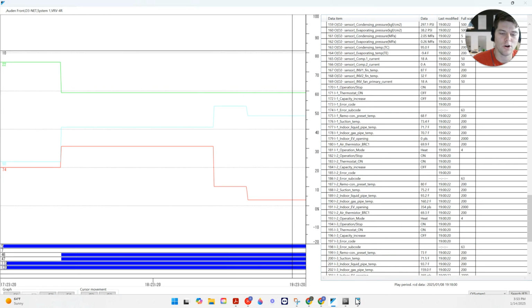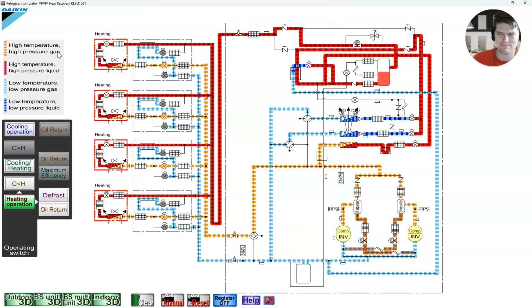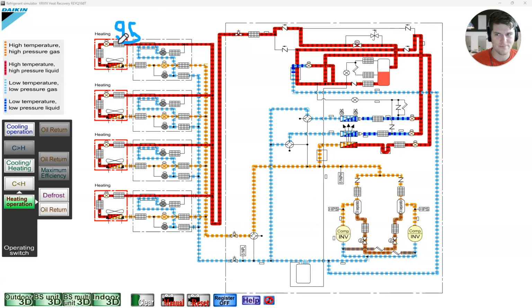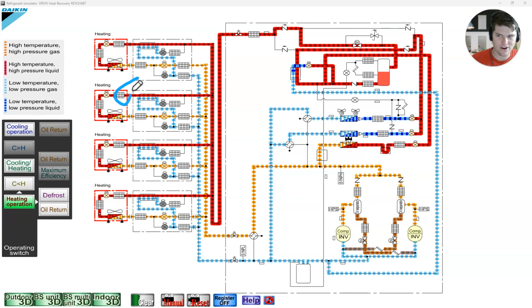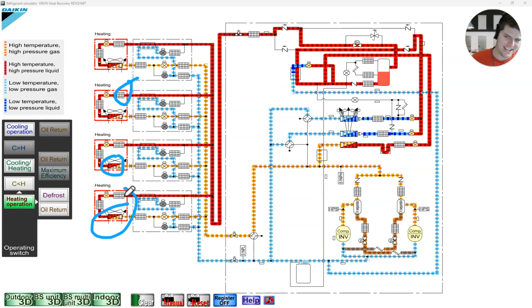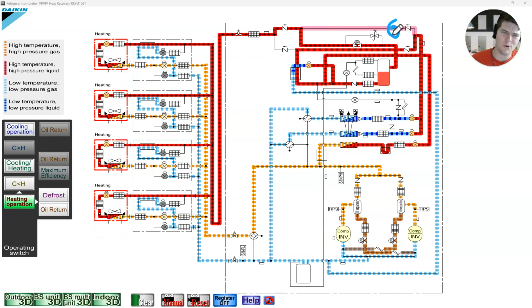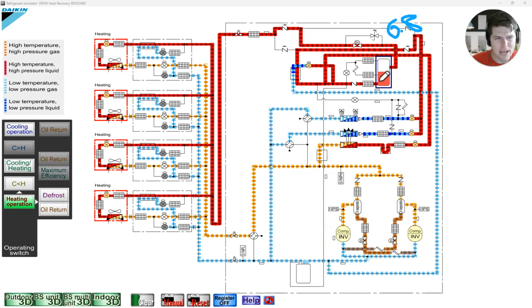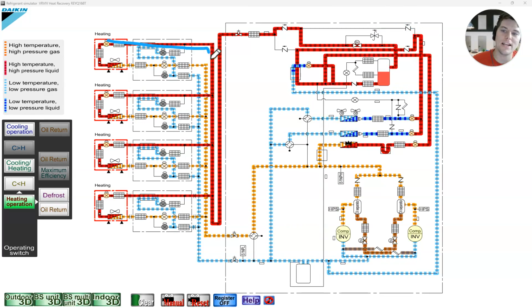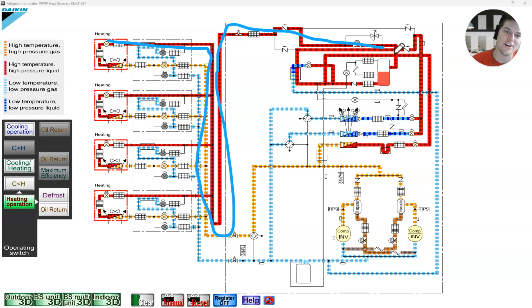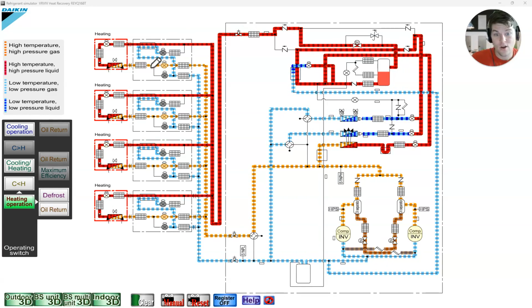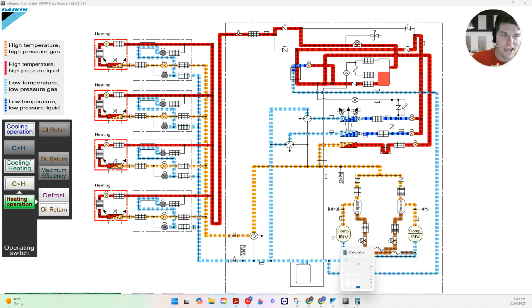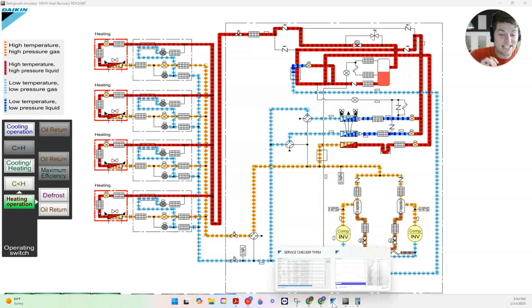Wait a minute. So if I go back over my animation, you're telling me that I have 95 degrees here and here and here and here, but I have 6.8 degrees here. How is that possible? What happens between here and here? I'll tell you. When we look at that 95 degrees, what does that tell us? It's hot, right? It's warm. But what is the quality of vapor, right? Is it superheat? Is it subcooled?